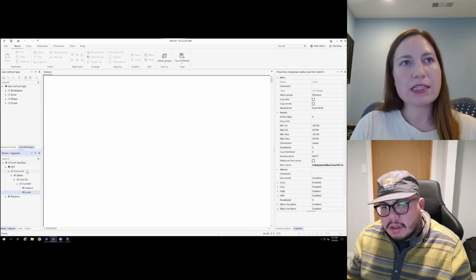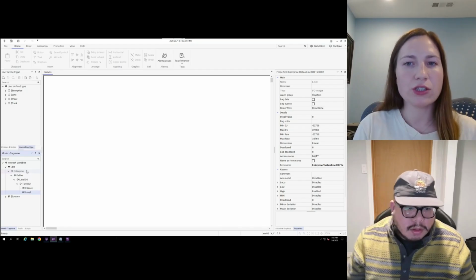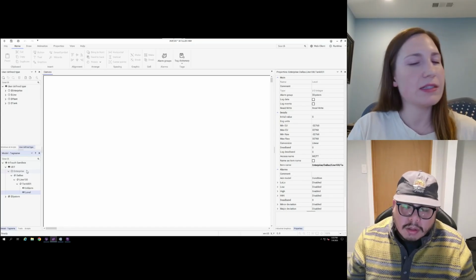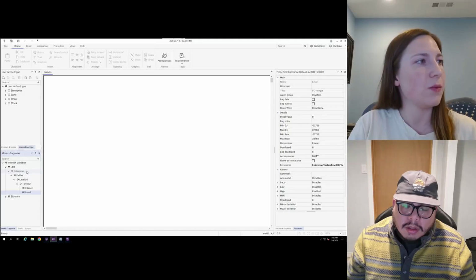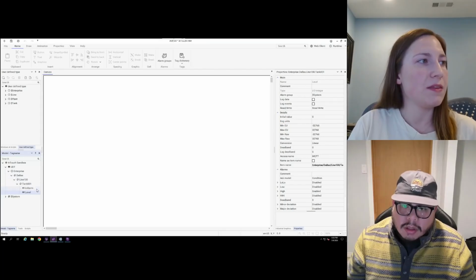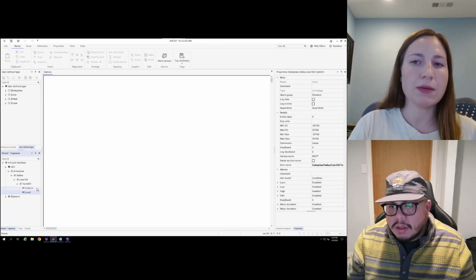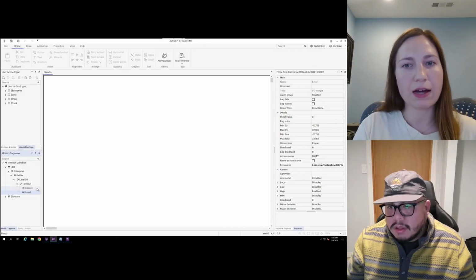What's really nice about being able to create this hierarchy is that I can make sure that my model here aligns with ISA 95 model standards. I demonstrated that here, where in this example I have my UDT with my enterprise, my plant, my line, my equipment, and then the tags for my equipment here. So now what this means is I create this model in InTouch that adheres to the ISA 95 standards.